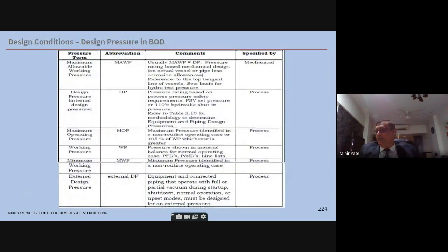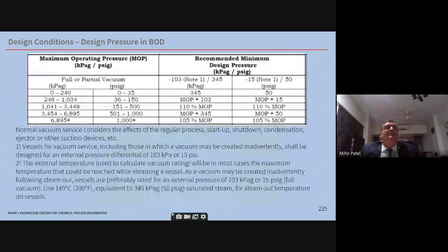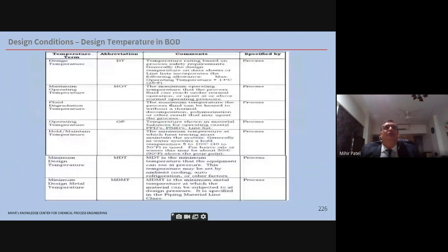Now in the BOD, basis of design, there are many things that are important. For example, design pressure. So here are just listed the various pressure terms and who they are specified by. So here you see only one is specified by mechanical. All of them are specified by process in the basis of design. Then design pressure, again, different companies have different standards, but this is just one standard I am putting here. How you define the DP, DT also, how you define the design pressure, design temperature.